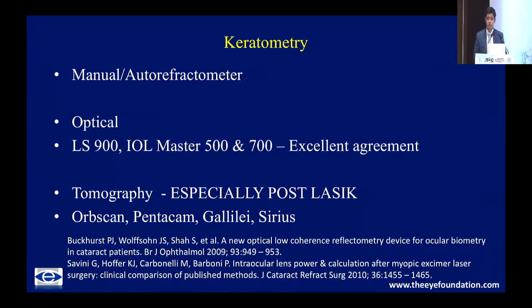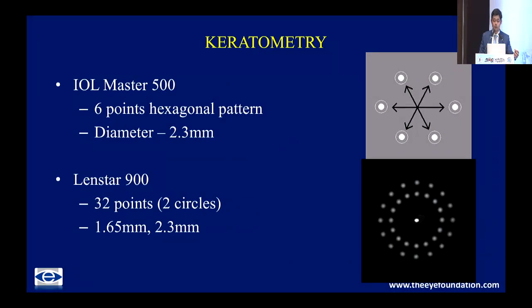There is excellent agreement between all the devices, any type of optical biometer that you may consider, whatever has been published in literature. Tomography is also useful, especially in post-LASIK patients. All the major tomographers, Pentacam, Galilei, Sirius, all give repeatable values. However, all our regression formulae are based on central data. And that is why we still prefer the keratometry taken from biometry devices rather than from tomographers from the SIMK values, which gives us a more average over a larger area of the exposed measured cornea. While this may be accurate in the keratometry itself, it's not directly applicable into the formulae.